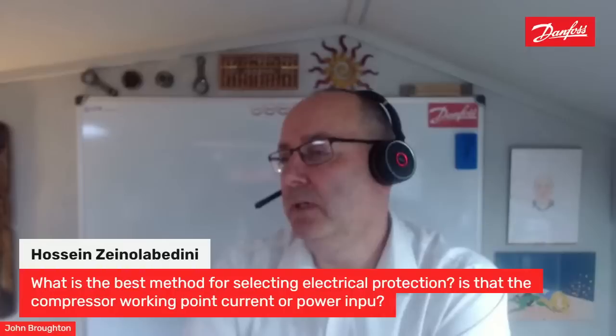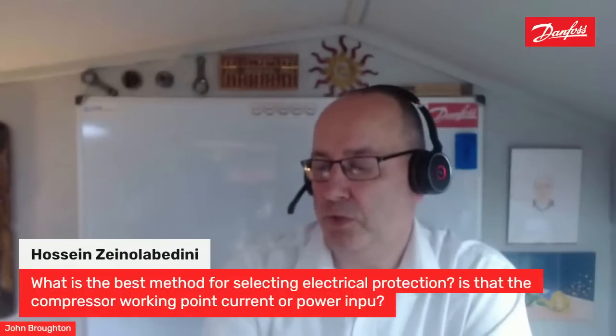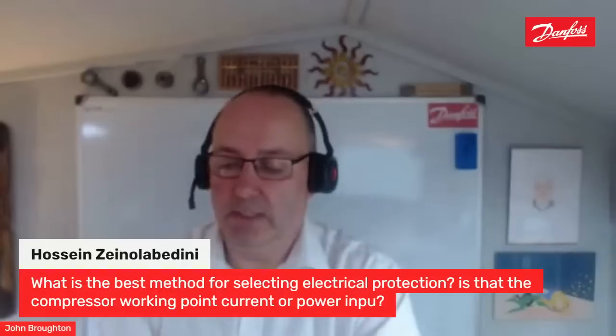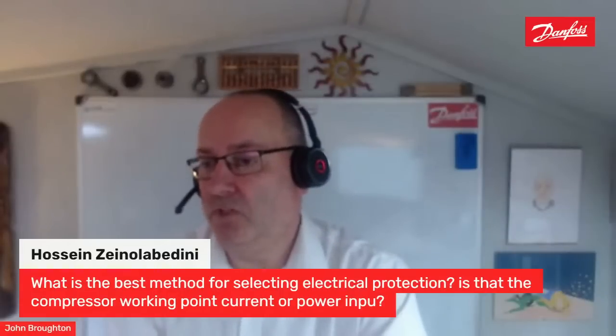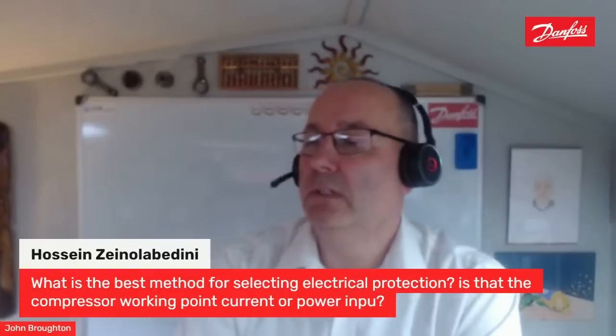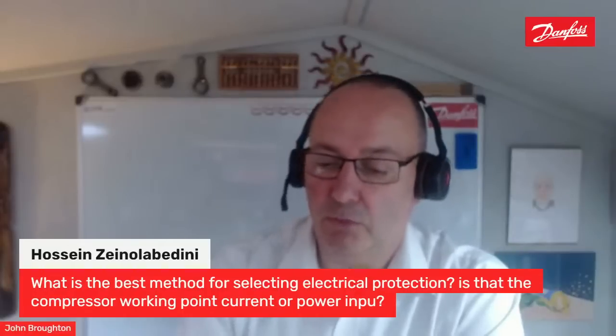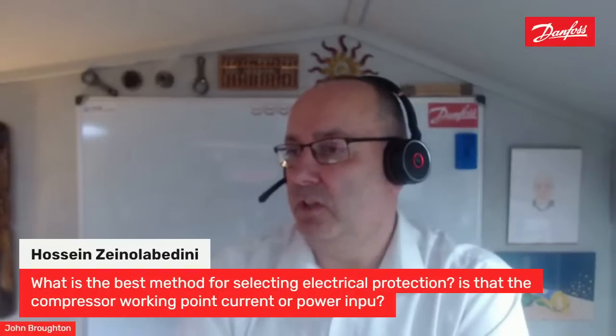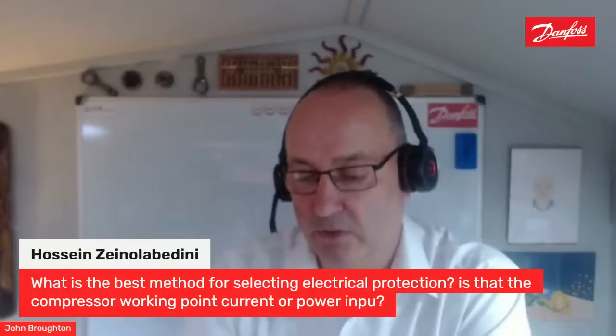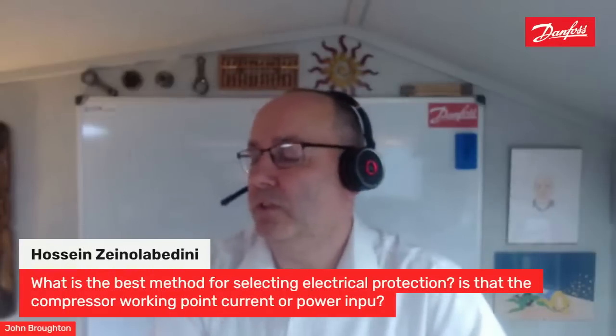So the suction pressure goes up, the amps go up, and you will get to the point where you are pulling more current than your compressor can cope with, and you want to make sure that you trip out on overload. If you don't, then you'll run the risk of damaging the electrical wiring within your motor, inside your compressor.